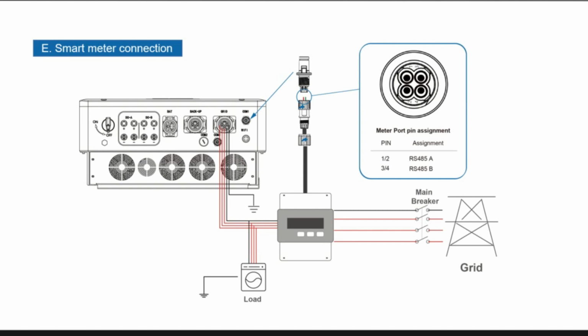And this is now wiring for the meter. The meter point goes in COM1 in here. See on the right-hand side there, meter port pin assignment, 1 and 2 are A and 3 and 4 are B, which goes back to COM1. You use the same points for wiring extra inverters up, in and out as you go along. I don't know whether it's 100% true, but it's unlimited. I don't know how many inverters is unlimited. I think we could get quite a few.